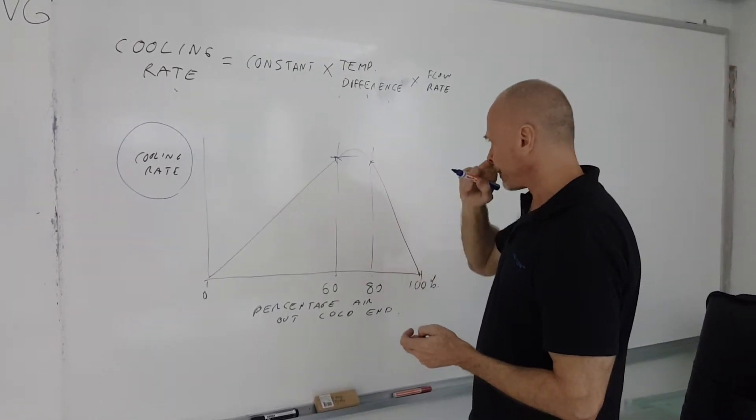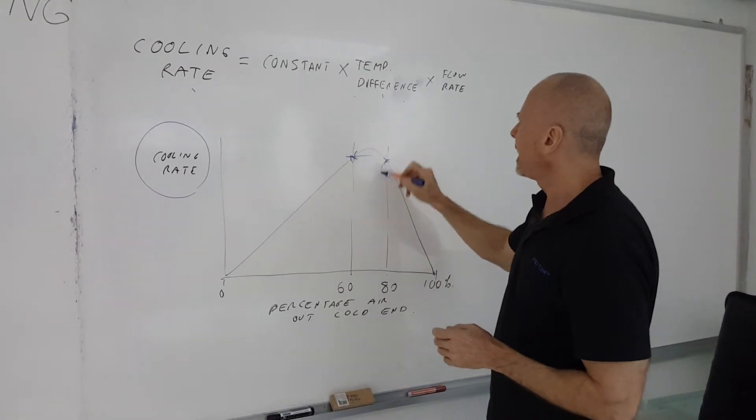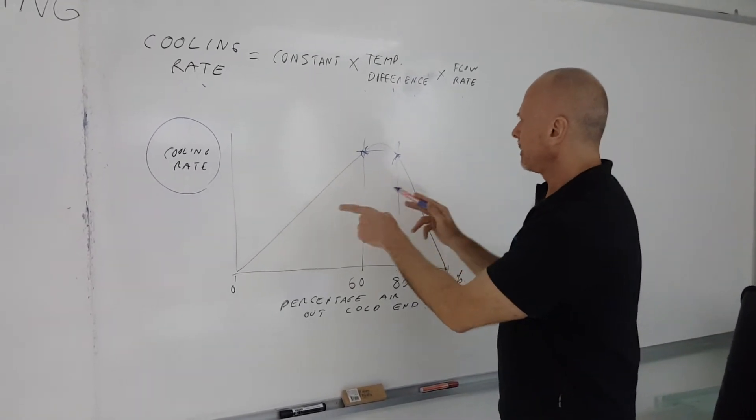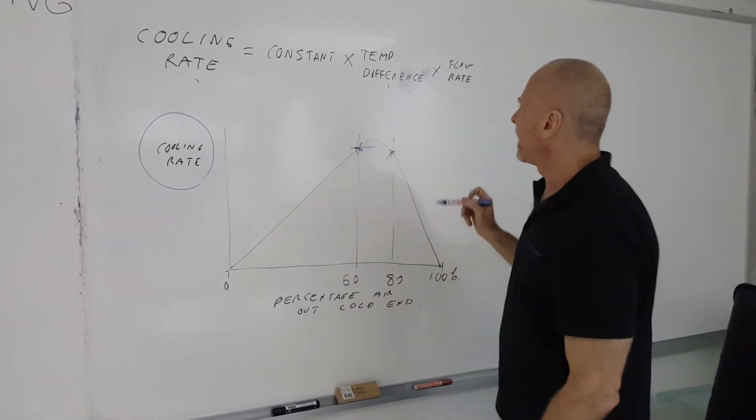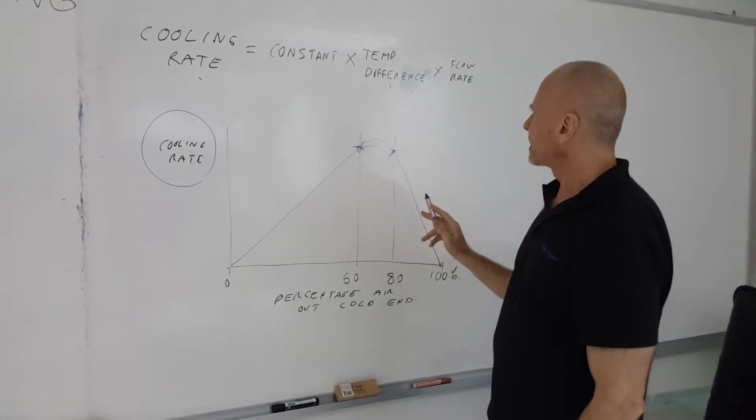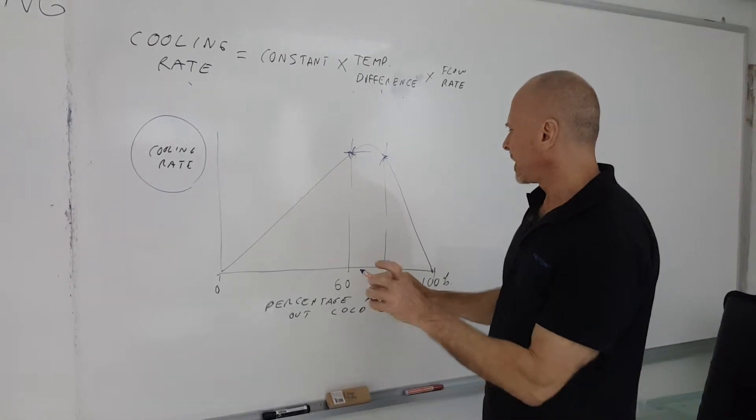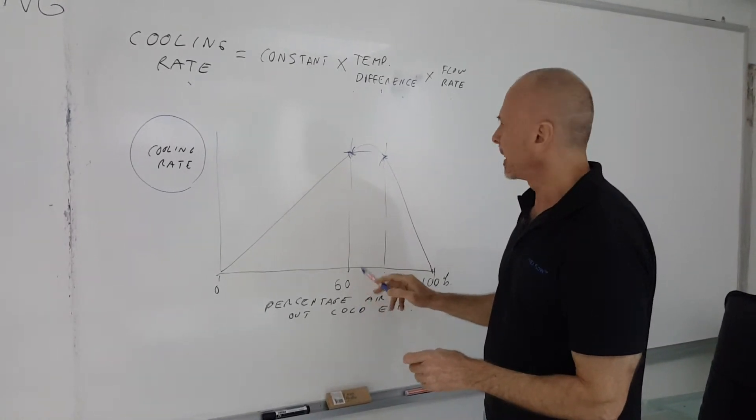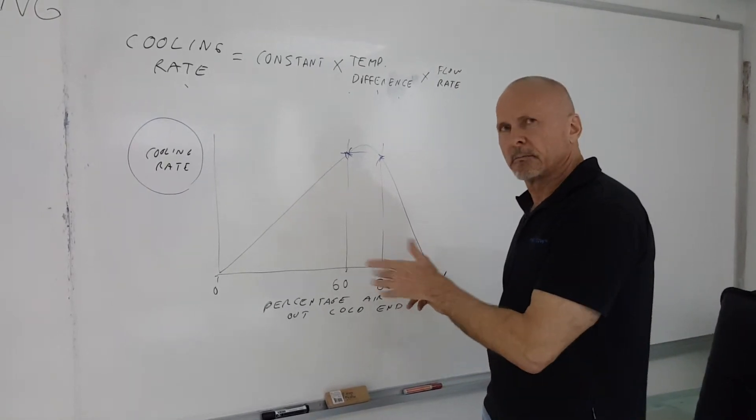Now, think about this. The best cooling rate was somewhere between 60 and 80%. And by the way, this can change too. This graph can wiggle. We found that if the reference temperature is very high, you're actually better off to have the percentage of the air off the cold end as something like 60%. If the temperature is cooler, you're actually better off to have it at the other end.